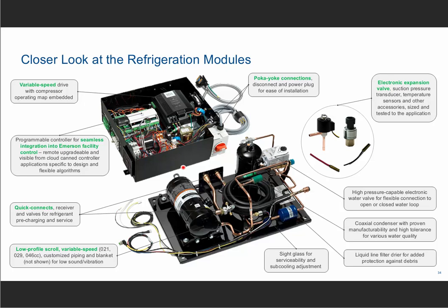And with this chart, I wrap up the session that is more related to 448, 449. I think I missed mentioning that over the presentation. With 448, 449, not having the charge limits you have for propane, you can cover most of your equipment in the indoor distributed architecture, as you're keeping that charge very localized at the equipment level. In those cases, they will vary between 1, 2, 3 pounds all the way up to 5, 6, or 7 pounds, but not much more than that. So you're a lot lower than that 50 pound limit that Andre mentioned earlier in the presentation.